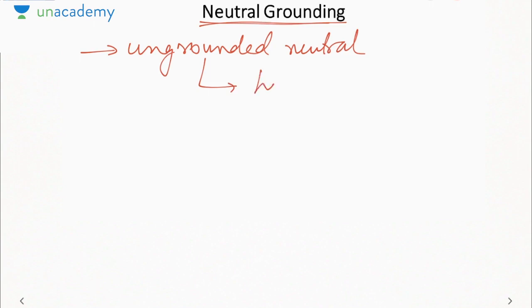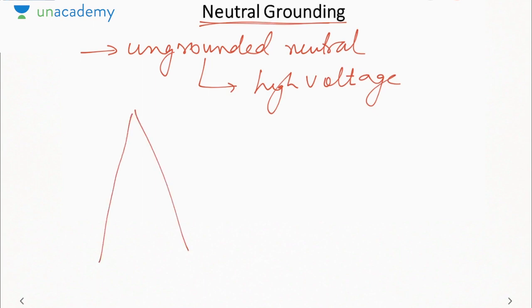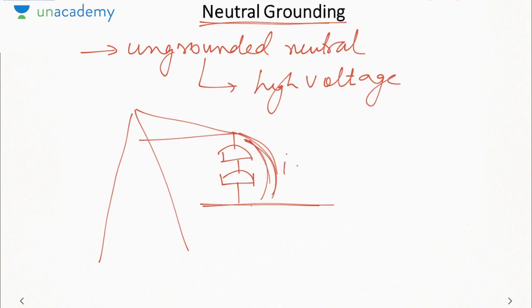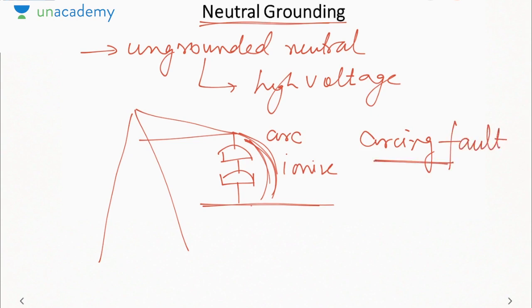Now when the voltage of the conductor is high, suppose we take the case of our overhead line. If the voltage of the conductor is high, then what will happen? The air around it will ionize, so there will be an arc formation. If an arc is formed, then it is called an arcing fault. Current will flow into the tower through the arc. That is called an arcing fault or an arcing ground. If you do not isolate the neutral, an arc can be formed along the insulator, which is also known as insulator flashover. So these types of fault are called arcing ground. That is why these are dangerous.